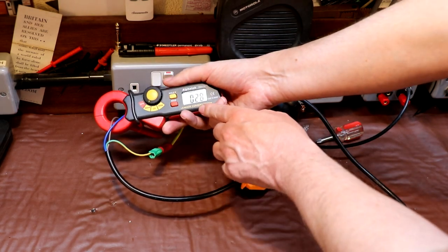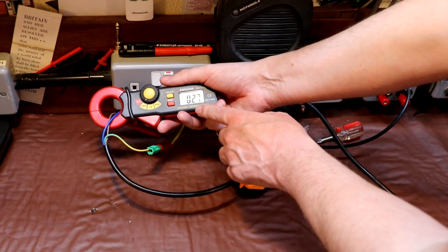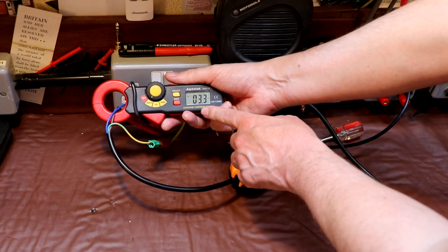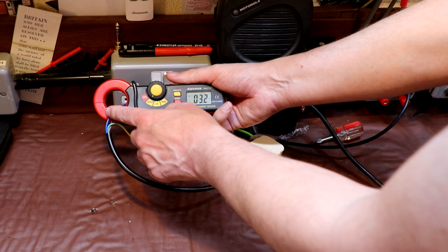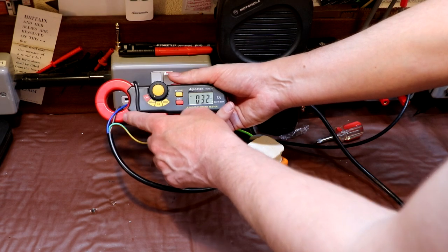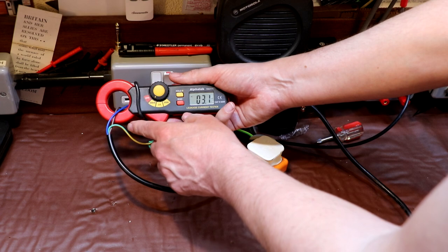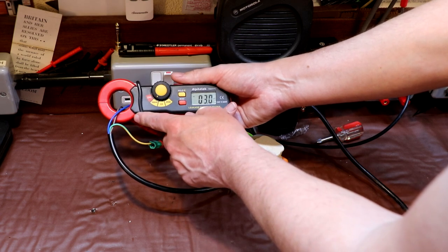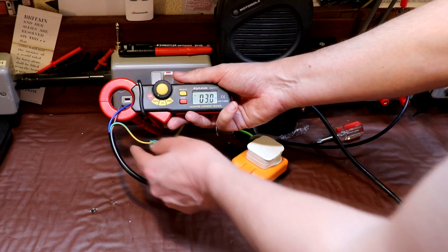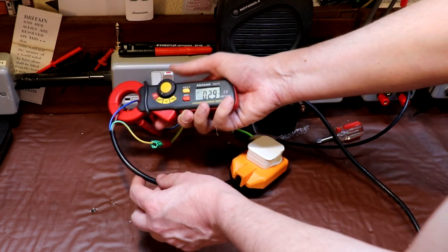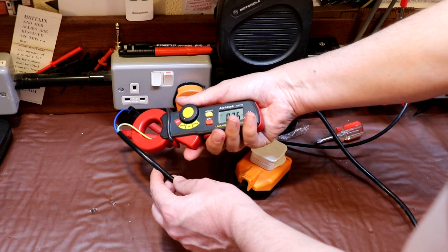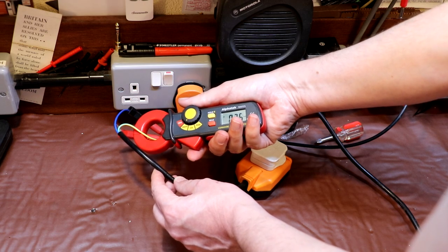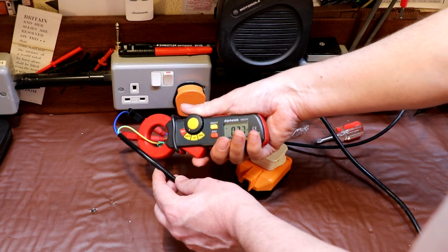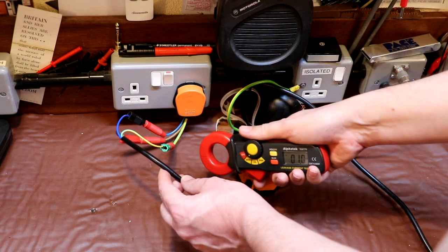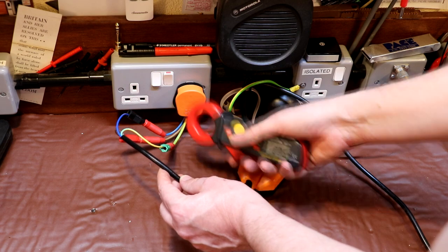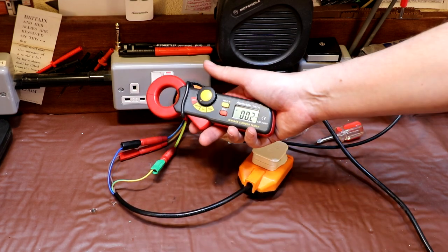Now this time we've got a reading here, and it's fluctuating a little bit, but hopefully you can see that it's about 3 milliamps. So I've got 3 milliamps of difference between the current going into the test equipment and the current coming out of it. Now that current is going somewhere. In theory it's probably going directly into this earth wire, so let's measure that. Measuring about 2.6, 2.7 milliamps on the earth wire itself. So you can definitely see we do have some current flowing into the earth system, but the KAIWEETS meter, because it doesn't have the resolution, couldn't see it.